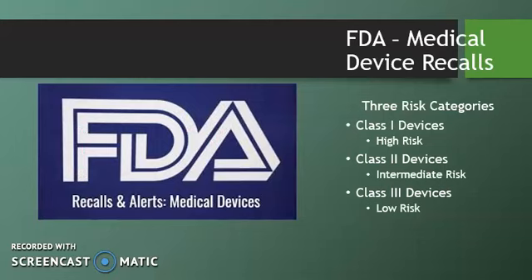The FDA has 3 risk categories related to medical device recalls. Class 1 devices pose high risk that the product will cause serious health problem or death, and the manufacturer must notify customers and recipients of the risk. Class 2 devices pose intermediate risk that the product will cause temporary or medically reversible adverse health problem. Manufacturer must notify customers and sometimes recipients of the risk. Class 3 devices pose low risk, and the product is not likely to cause adverse health consequences, and the manufacturer must notify customers. Examples of recent recalls include breast implants, defibrillators, endotracheal tubes, and surgical staplers.